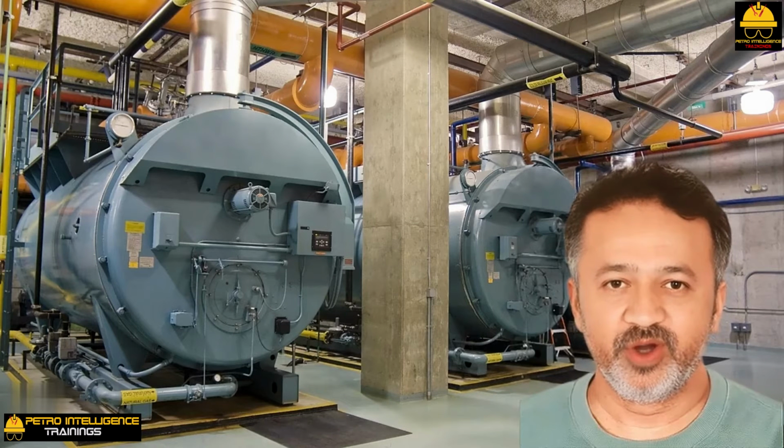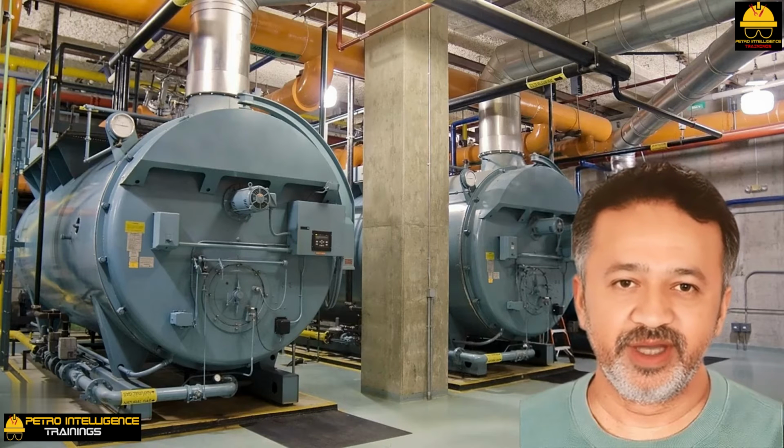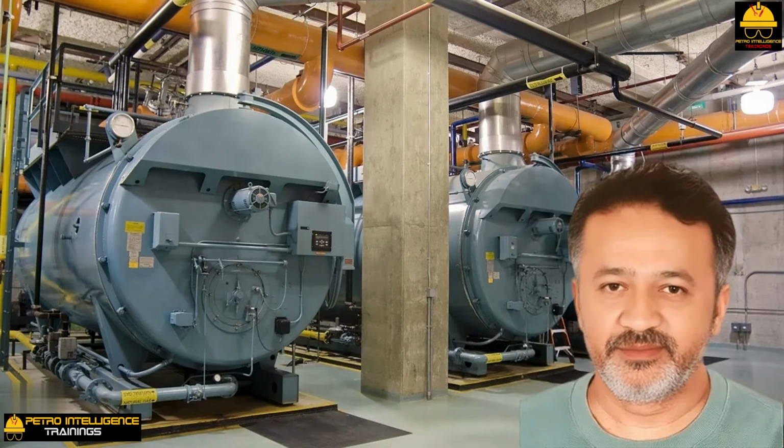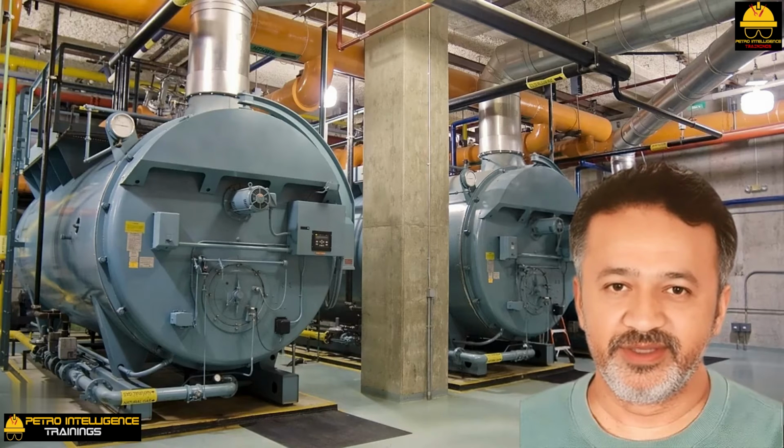The worst part about the whole incident is not that the supplier was blamed for the client's operating errors. It was that the steam was being superheated for no purpose. All of the steam was being used for hydrocarbon product stripping, where steam superheat is not important.